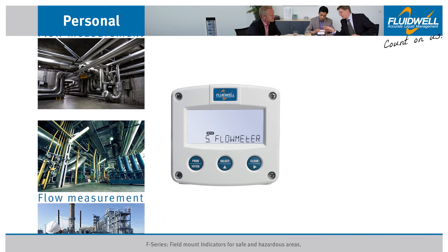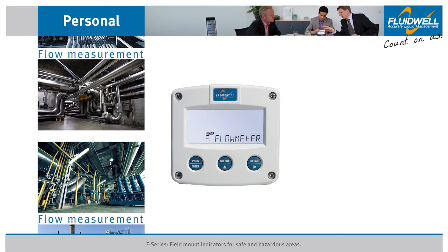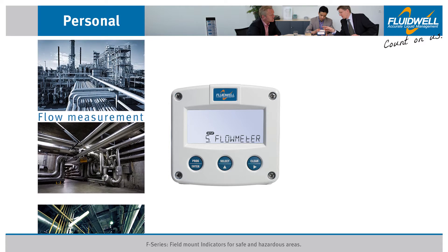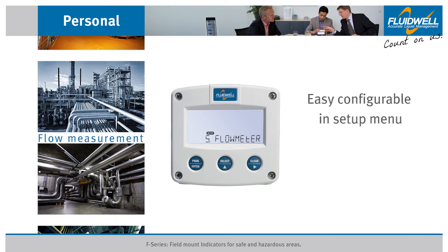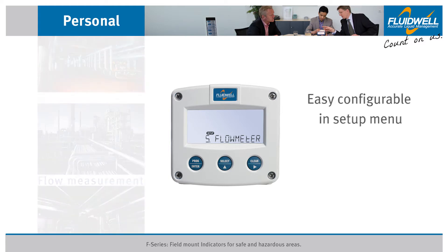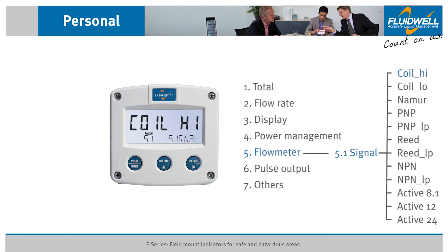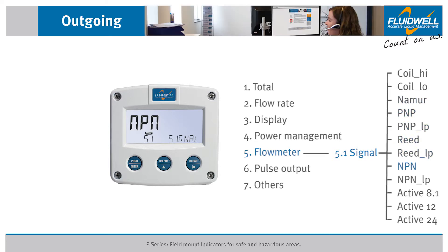For flow measurement, the F-Series accepts most signals from almost any flow meter. The various pulse input signals are easy configurable in the setup menu, like Coil, Namur, PNP, Reed switch, NPN or active input signals.